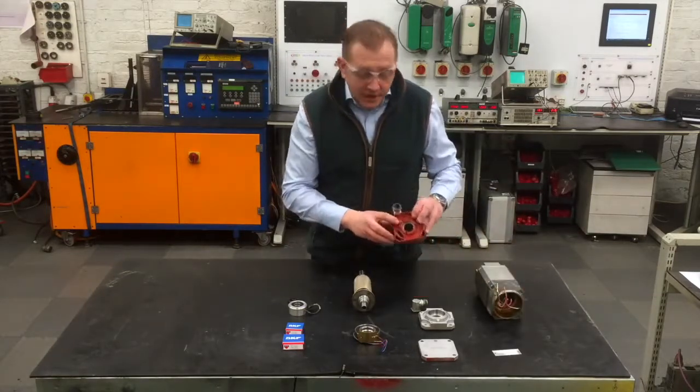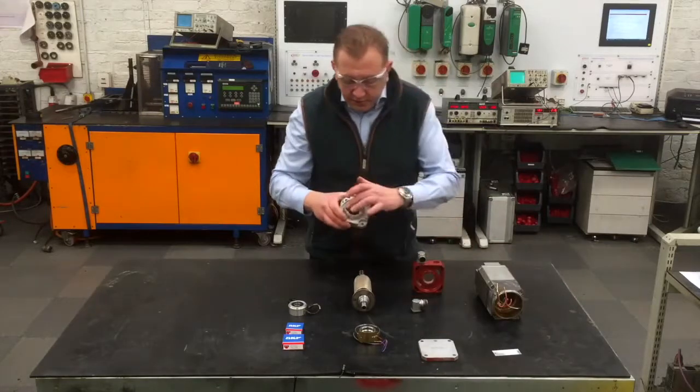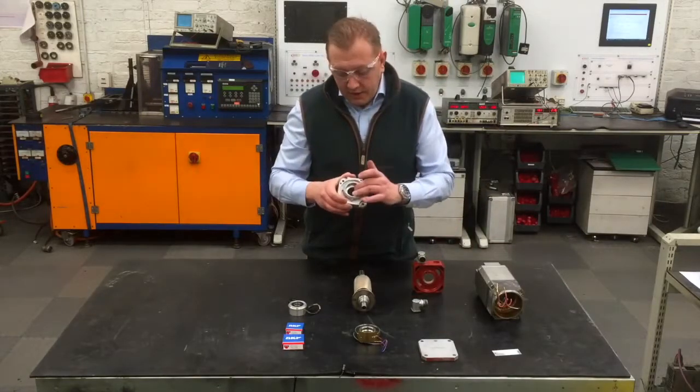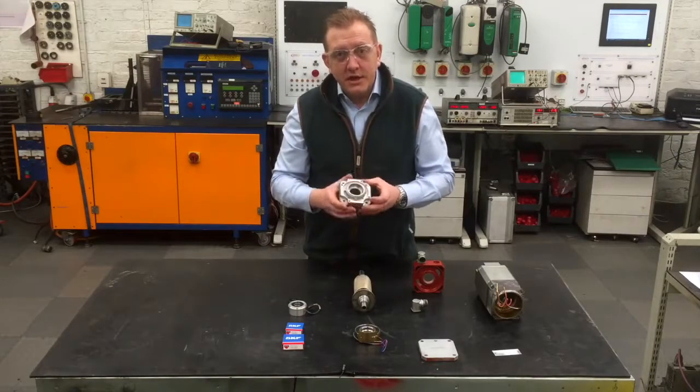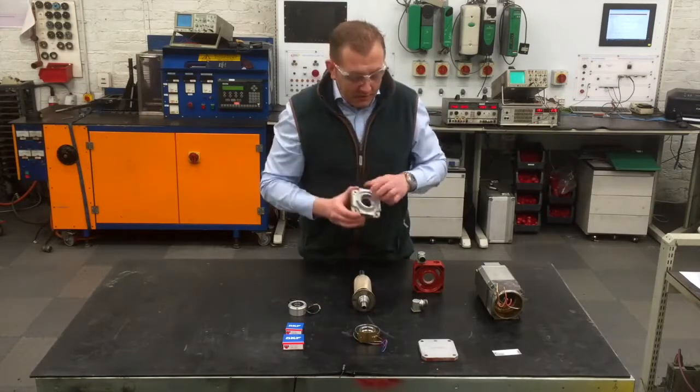The end shields have been checked and this is the drive end shield where we had to remachine. We have shrunk fit a sleeve in here and we have machined to size. And we have checked the size on the CMM machine so we know it is the right tolerance for the bearing.